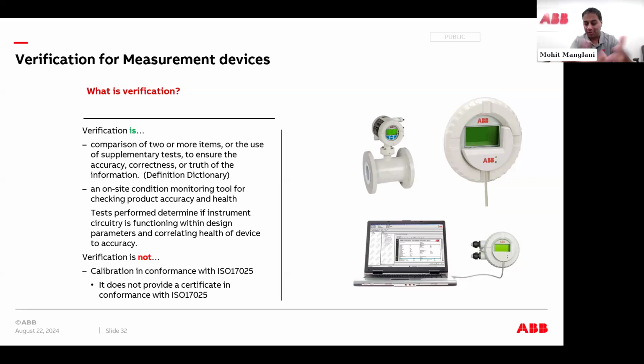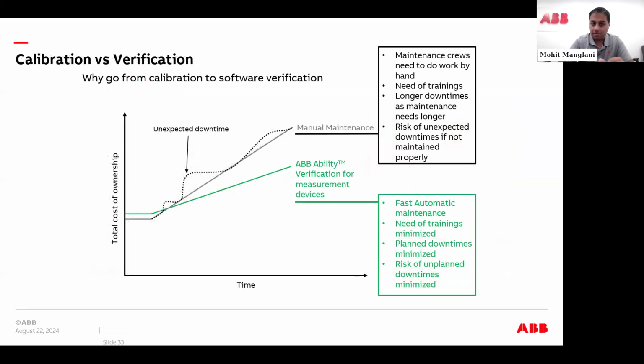So I've heard a lot of end users or customers say, can you come out here and calibrate my device? Not possible. Calibration has to happen in a known flow facility. Verification is what most people are doing out in the field today. This verification is the capability, and you can do it all in the field while your process is running. There's limited downtime unless you're testing the outputs. So just to share that out there. If you look at calibration versus verification, calibration takes a lot more time and it adds to the cost of ownership. Verification, I apologize, it says ABB Ability Automatic Maintenance: one tool, one software, one piece of hardware. You can plan for downtime if you need it. And if you do have a situation where you need to validate the health of the device, you can do it on demand.